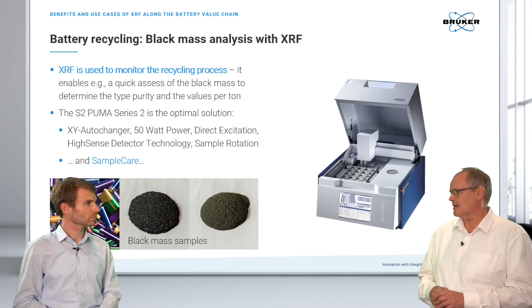Yeah, it means we receive this material and we want to determine the commercial value, especially how much cobalt, manganese and nickel is inside. The benchtop XRF instruments are ideal. The S2 Puma has enough excitation power to determine all the necessary elements. On the other hand, it also has some precautions, because we learned these are pretty nasty samples and there must be some precautions in the instrument.